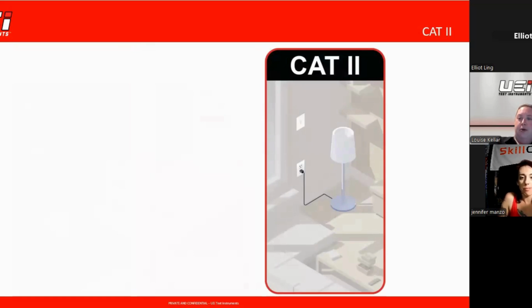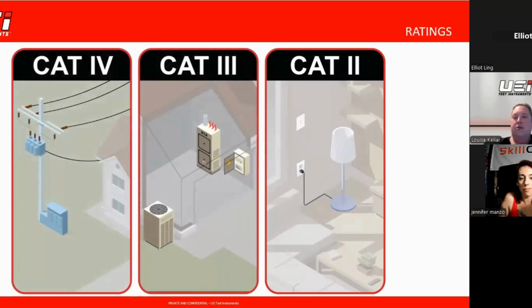Why are those important, and why do so many manufacturers put a category 4 rating on our meters? What that category 4 rating really does for you is give an extra level of protection. If you only have a meter rated category 3 and something happens, we've seen it, something's miswired, something jumps from the power running a lot higher than it should, having a category 4 meter helps with that protection.